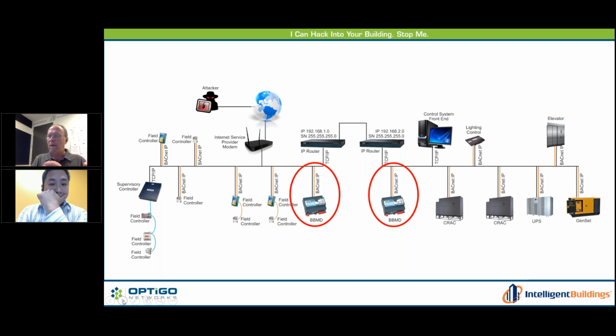I was talking about front ends, about managing your passwords and doing that kind of thing. That was great. But now that the BBMD has come to light - not that it hadn't come to light for us, but it's showing up in the bad guys' realm - the BBMD, which means BACnet Broadcast Management Device, exposing that to the web means there is no username and password. Every device below it is exposed now. So you don't even have to have all the other IPs. If you can get to the BBMD, you can get to everything below it.